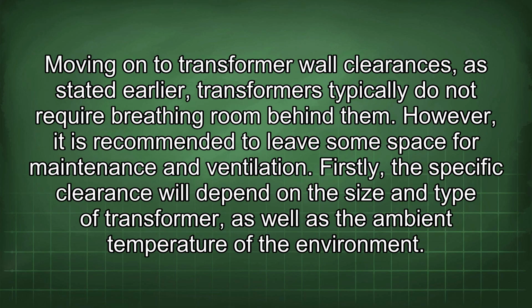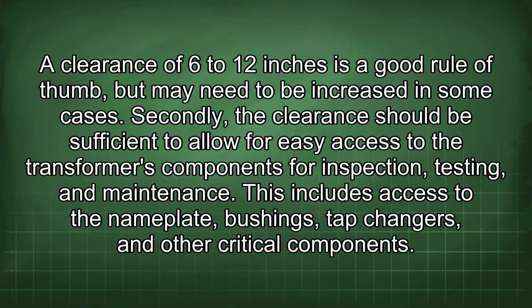Moving on to transformer wall clearances. As stated earlier, transformers typically do not require breathing room behind them. However, it is recommended to leave some space for maintenance and ventilation. Firstly, the specific clearance will depend on the size and type of transformer, as well as the ambient temperature of the environment. A clearance of 6 to 12 inches is a good rule of thumb, but may need to be increased in some cases.